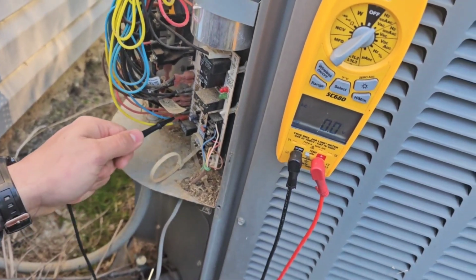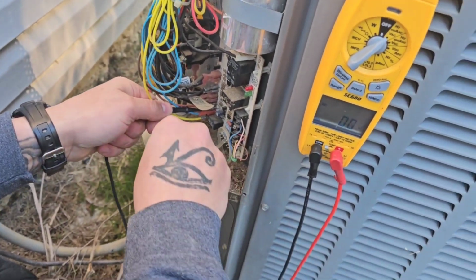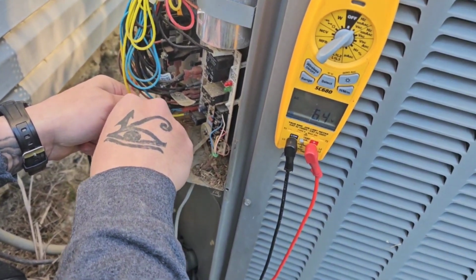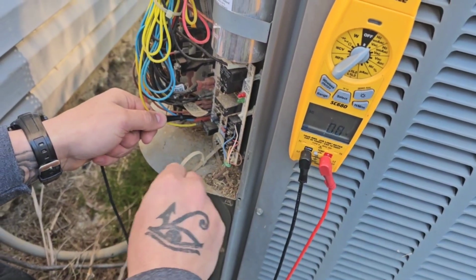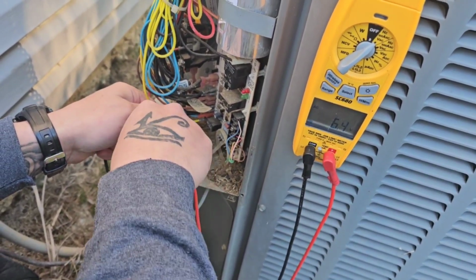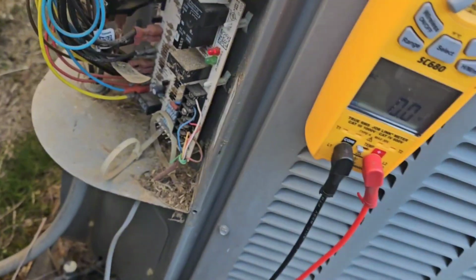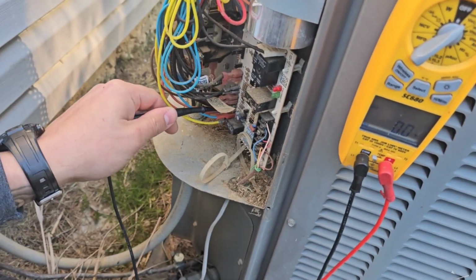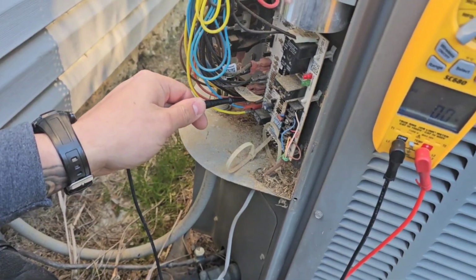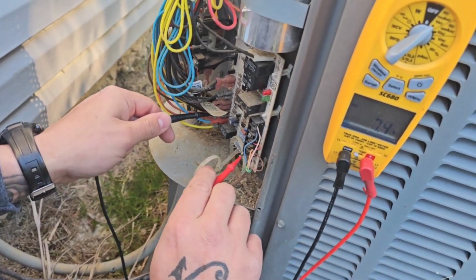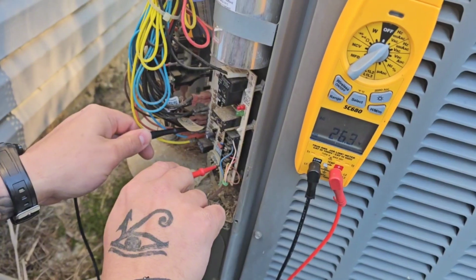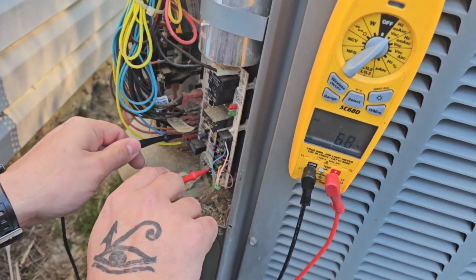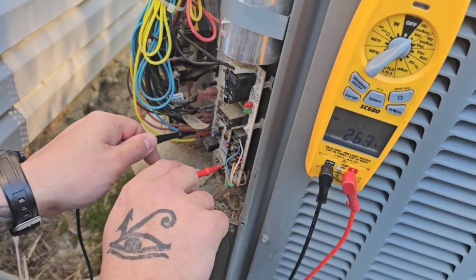To ground? No, not to ground. Oh, check the ground. Make sure we got 24 volts anyway. Scratch your probe a little bit on the metal. All right, put your one probe there again. Now go to the Y1 wire, yep. So that's 24 volts right there. And yep, 24 volts right there.